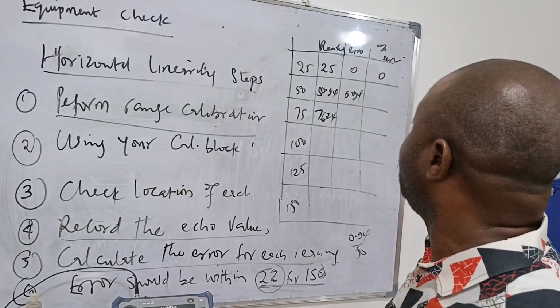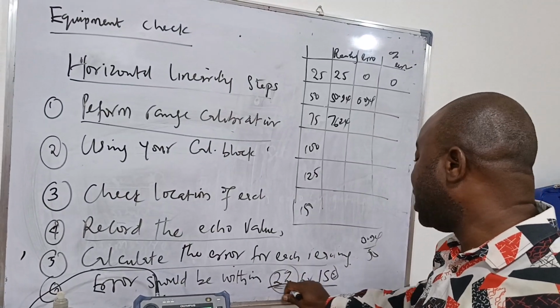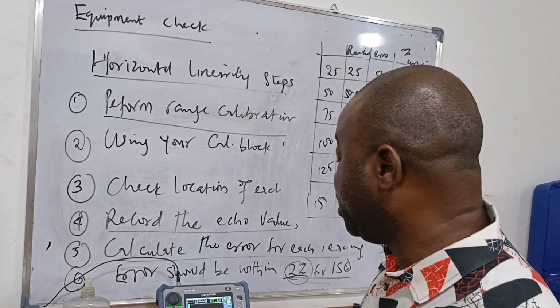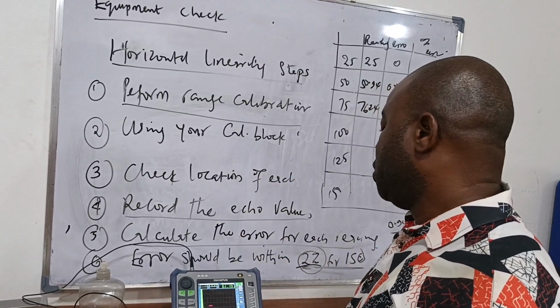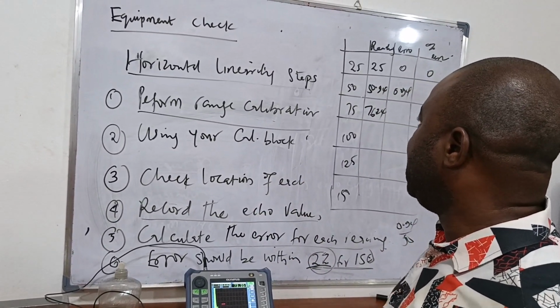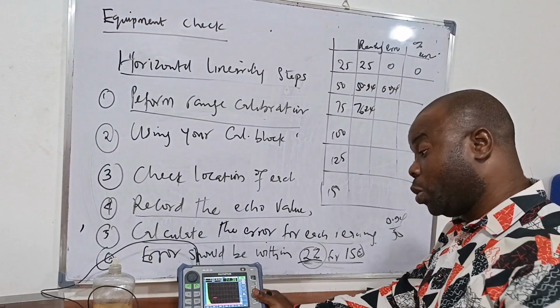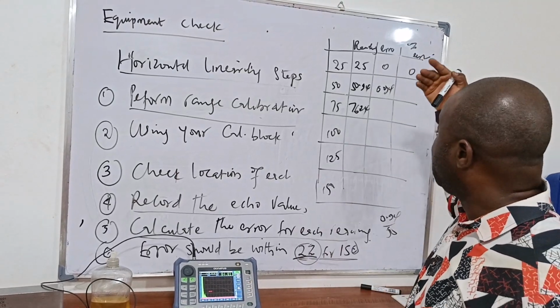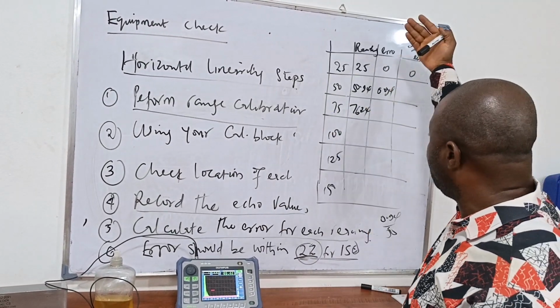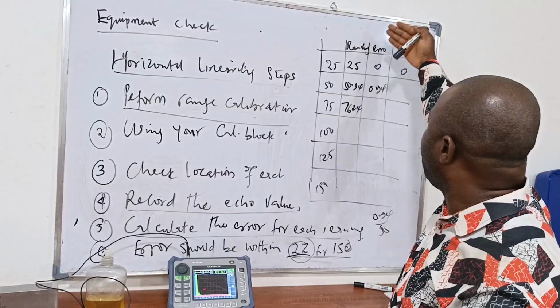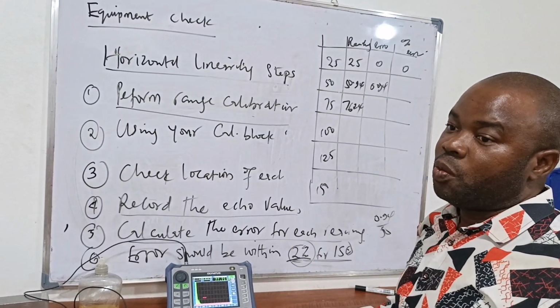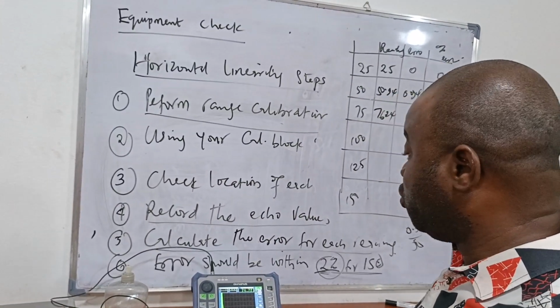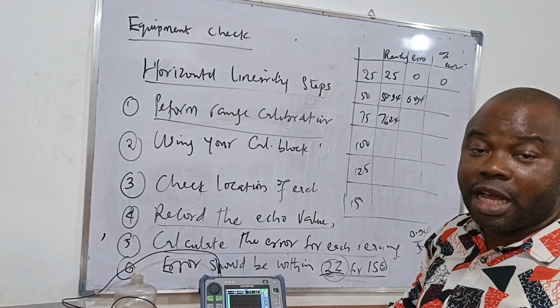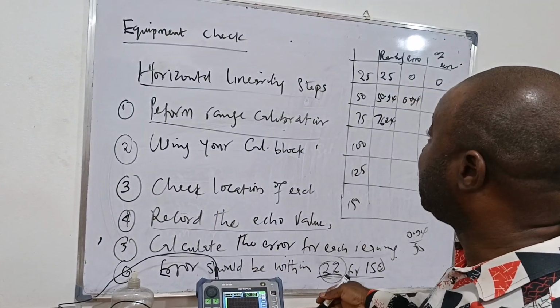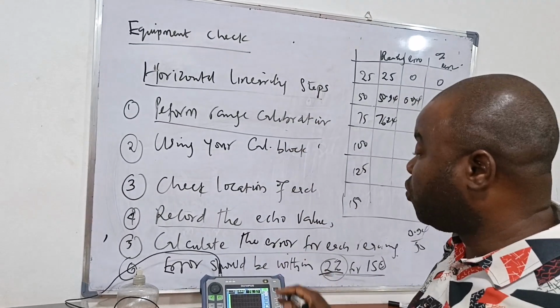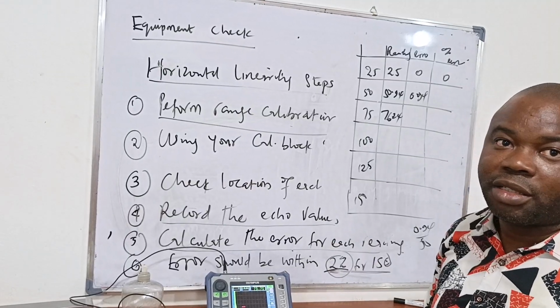After doing all that, you check the value. If they are less than 2%, it means your machine is horizontally linear. Linearity is okay, so that settles it. Some procedures will give you a spreadsheet where you can record this value. Or if you go to certain jobs, you'll be given sheets to do your linearity, check your horizontal and vertical. So that settles horizontal linearity.